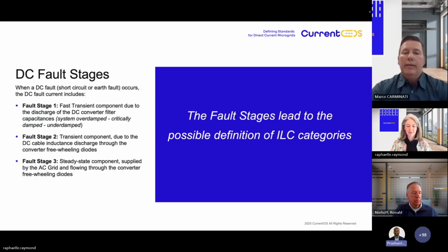So when we talk about the DC fault, both short circuit and earth fault, usually we can have up to 3 fault stages. The first and second stages are transient component, and instead the third one is a steady state component. The first stage is a very, very fast transient component, and basically it is due to the discharge of the DC capacitor, as we have seen before, installed on the DC side of the AC-DC and the DC-DC converters in our DC distribution system.